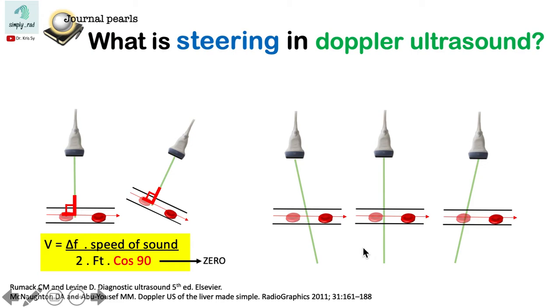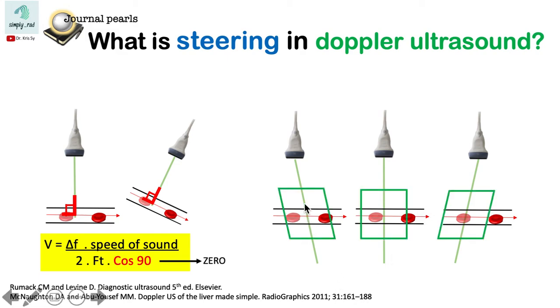So what we do is to send the pulse at an angle, just like this. What is usually available is we can adjust the angle to 20 degrees or minus 20 degrees. These pulses are parallel to the steering boxes that we see.